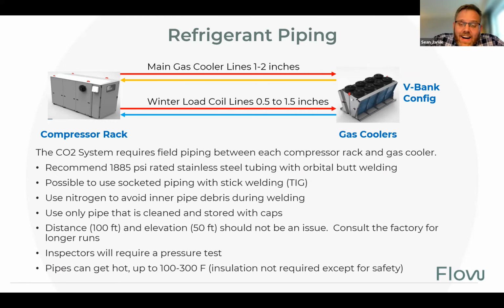The pipes can get hot though, and we're talking discharge temperatures between 200 degrees to 300 degrees. So you are going to want to insulate those lines just from the fact of nobody bumping their head and instantly branding themselves with something fun. Or I think the Seattle Energy Code also dictates that we should insulate with a minimum of 1/2 inch to 1 inch on any refrigerant line, regardless of what it is. So it's a really nice thing for safety, but it's not necessarily required for efficiency.